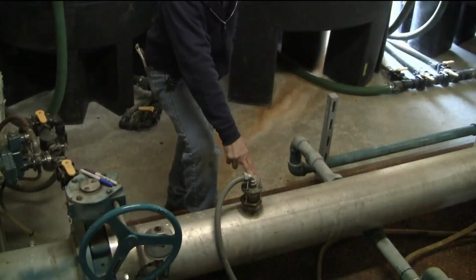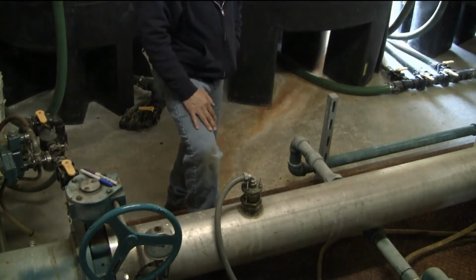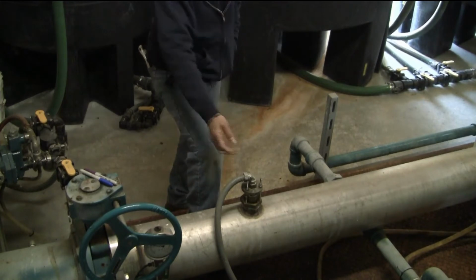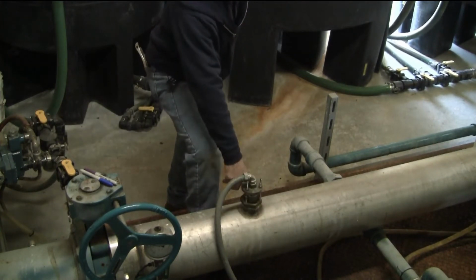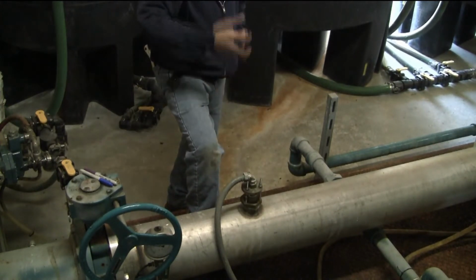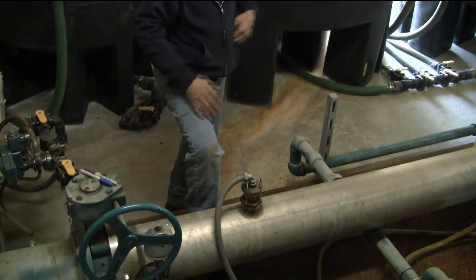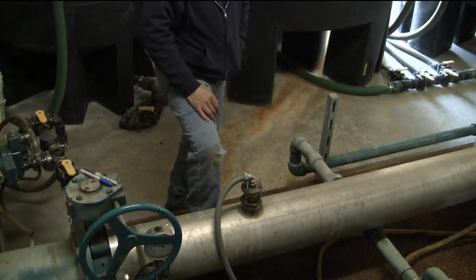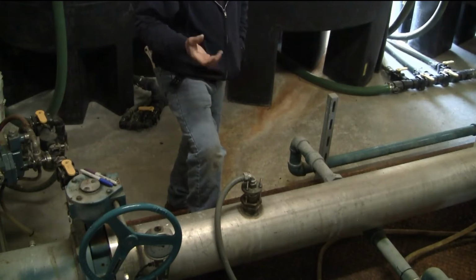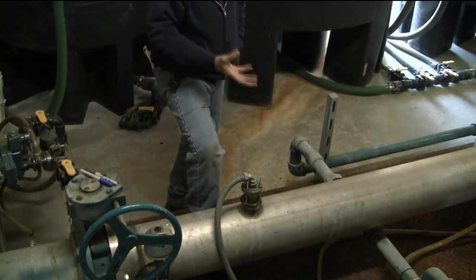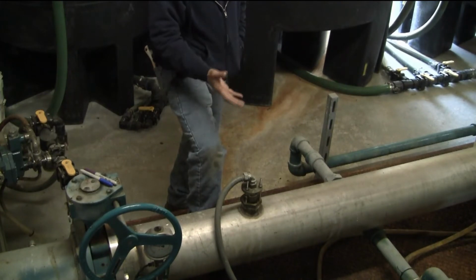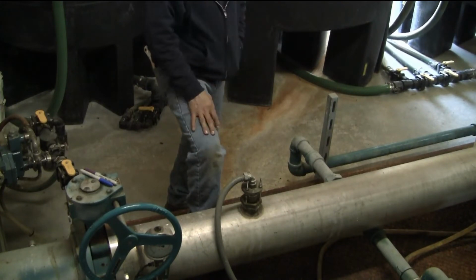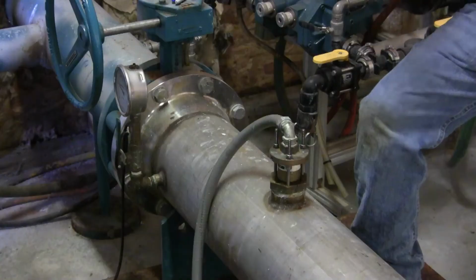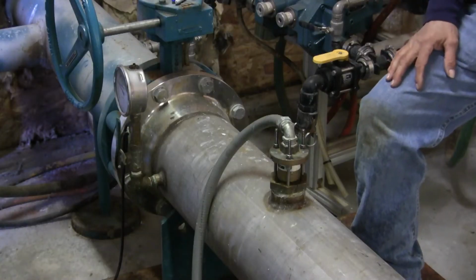We like to pull the flow sensor and make sure it's in good shape. A lot of times there's a moving wheel on the bottom. It's in the flow of water. You pull it out and make sure it's still in good shape. A lot of times, depending on the water quality, it can build up with mud. I've seen it already where it doesn't move at all. We're not getting any flow on the reading on the door. We pull it out and it's caked in mud.